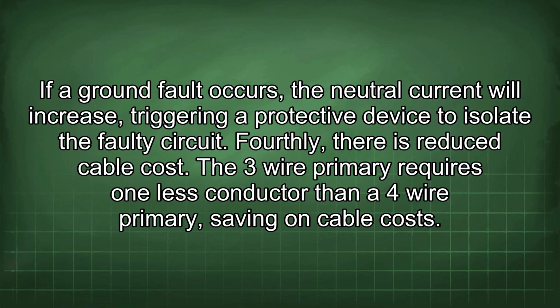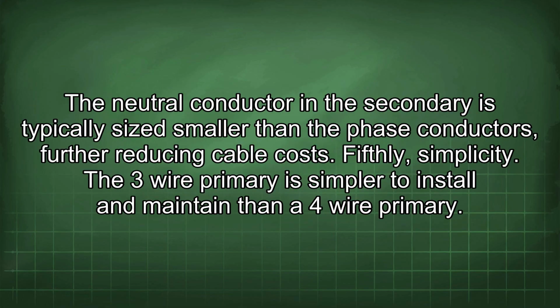Fourthly, there is reduced cable cost. The 3-wire primary requires one less conductor than a 4-wire primary, saving on cable costs. The neutral conductor in the secondary is typically sized smaller than the phase conductors, further reducing cable costs.